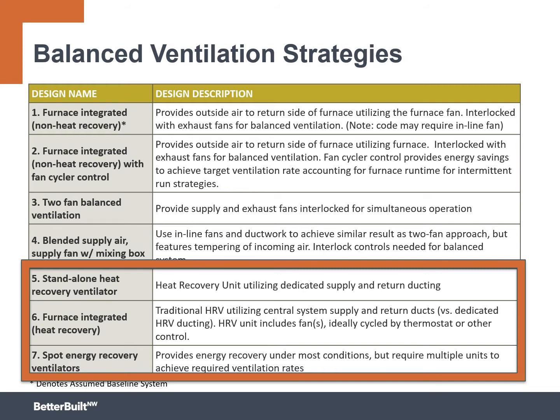There's spot energy recovery ventilators. We are only going to touch on these a bit today because for code's sake, these actually are very low flow and it may take 2 or 3 or 4 of them to actually meet the ventilation requirements for most homes. But effectively, these are a single unit, pipes air in and out, and then blows air in directly and takes air out of a central location or a single spot in the home. So it's not going to do much for distribution for you, but it can be balanced. We're really going to talk about standalone heat recovery ventilators and furnace integrated heat recovery ventilators moving forward.